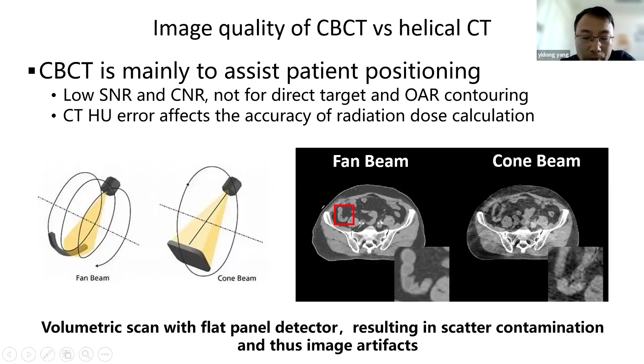So in the clinic, cone beam CT is mainly used to assist patient positioning. Compared to fan beam CT, it has a relatively low signal to noise ratio and contrast. So it's not suited for direct target or OAR contouring. Also, the CT number, or Hounsfield unit, error is larger than from fan beam CT. So usually we do not use cone beam CT for direct dose calculation. But after we improve the image quality, we can expand its functionality. One important point is that this volumetric scan can result in scatter contamination and also image artifacts.